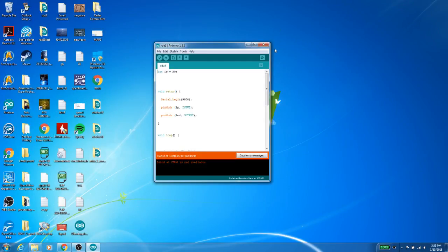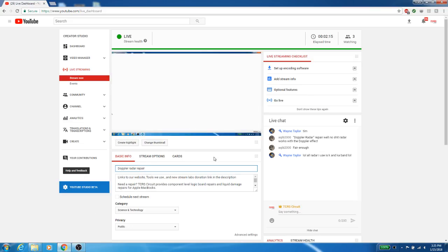Now, a couple things can happen here. What's most likely happening is our transmitter. The board on the transmitter is responsible for sending our analog signals back to the logic controller. If that does not get any of the analog signals in, it will not have anything to output to the serial on the computer, so you'll get a blank screen. So what we're going to do is go ahead and change out the transmitter and control board, and I'm going to show you here through the microscope after I show you the issue.